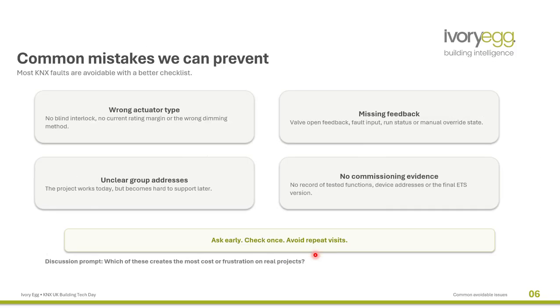Now we want to talk about common mistakes we can prevent. Wrong actuator type - for example, about the load as I mentioned before. We want to control the blind but we have an on-off actuator, so it doesn't provide interlock options. For an AC motor, when you energize the right rotation, the left rotation should be off, and vice versa - this is very important.